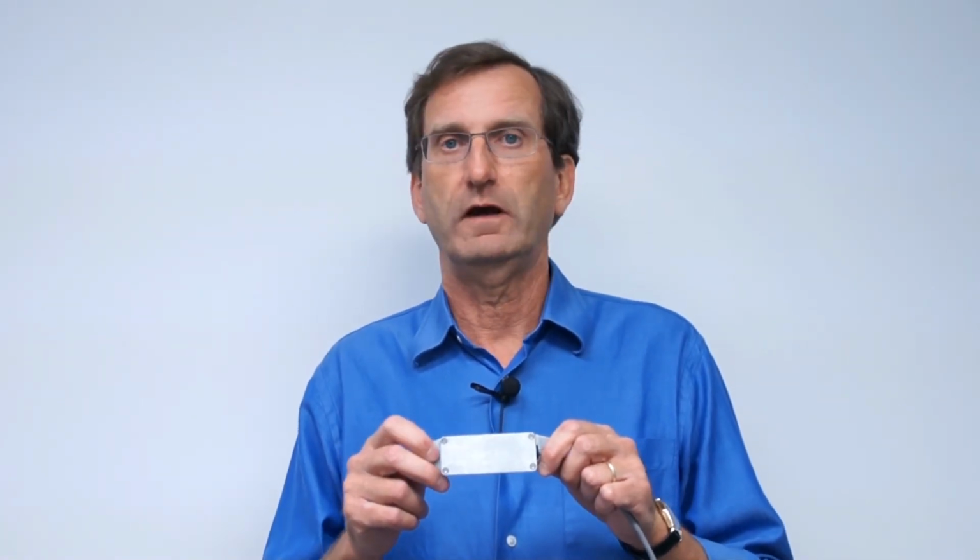Now, rather than trying to send that huge amount of data over the air to somebody that's never going to look at it, we've applied the most advanced research in vibration monitoring on rotating equipment to break that data down into 6 data points, into acceleration data, velocity data in both the rotational direction and the axial direction. And the research has shown that those 6 data points can be highly effective in tipping off a change in the process or in the machine that might predict impending failure.